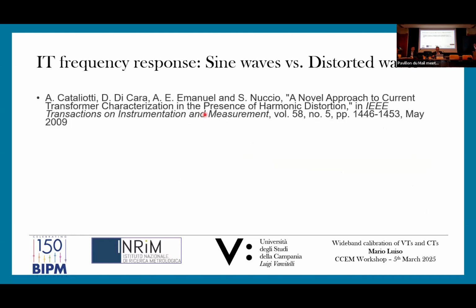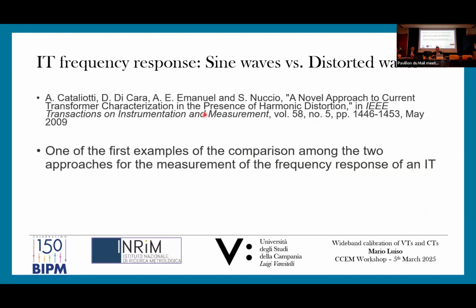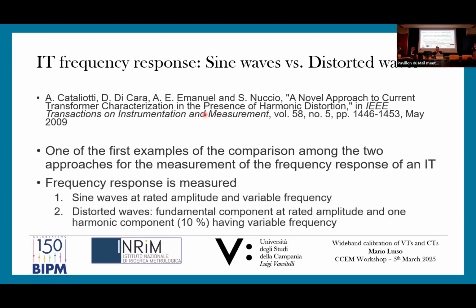But we have to wait until about 2009, when colleagues from University of Palermo maybe for the first time gave in literature an example of the comparison among the two approaches for the measurement of the frequency response of an instrument transformer: with sine waves, having full ranges but variable frequencies, and with distorted waveforms, so waveforms composed of a fundamental tone having the rated amplitude and one single sweeping harmonic component at 10% amplitude and different frequency.